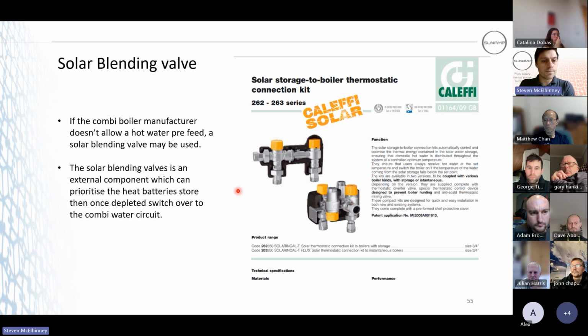That's one there. So the blending valve is an external component which can prioritize the heat battery's store. Then once the battery's depleted, it switches over to the boiler circuit, and then the customer gets the combi functionality. I see a few jobs like this. The customer doesn't have a time boost setting. They just rely on the solar for the summer, and they might get a trickle charge of solar in the winter, but it's the boiler that's picking up the heavy work throughout the winter, and they're happy with that. They're still making a saving.